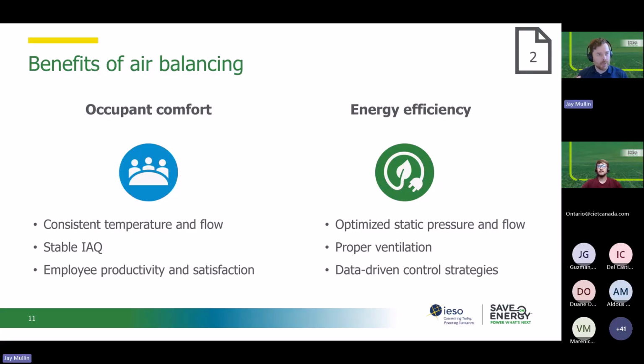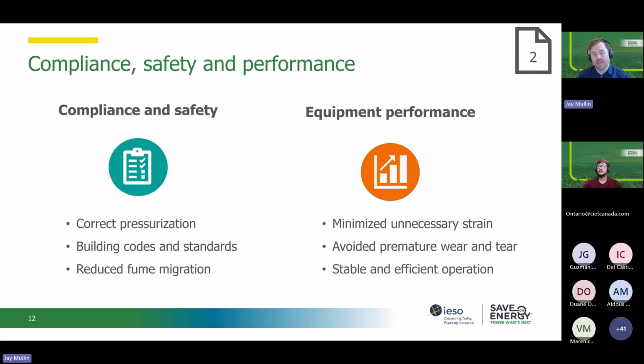And going through the process of air balance studies can also support data-driven control strategies like demand-based ventilation that match airflow to occupancy or production needs. It can also be important for compliance and safety, ensuring that you have the right pressurization in critical spaces like labs, clean rooms, paint booths, and help maintain building codes and industrial standards for ventilation and safety. And it can also reduce risk of fume migration or exhaust backflow, protecting workers and products.